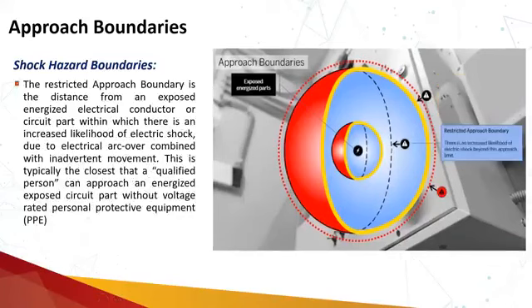What is the restricted approach boundary? The restricted approach boundary is the distance from an exposed energized electric conductor or circuit part within which there is an increased likelihood of electric shock due to an electric arc over combined with inadvertent movement. What are the chances of electric shock? I might not be touching the electrical equipment, conductor or circuit part, but the chance of electric shock is there due to the arc over phenomenon and inadvertent movement. So this is typically the closest that a qualified person can approach energized exposed circuit parts or conductors without voltage rated personal protective equipment. So if any qualified person needs to cross this restricted approach boundary, he will be wearing voltage rated personal protective equipment, and it is a mandatory requirement.